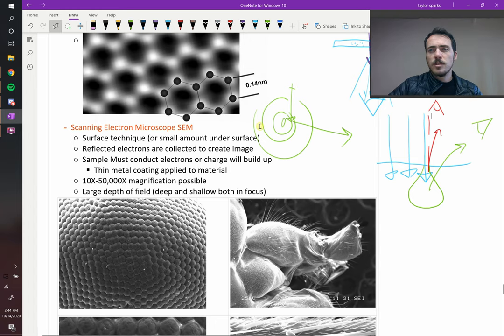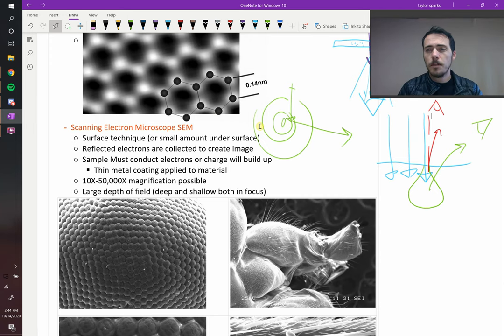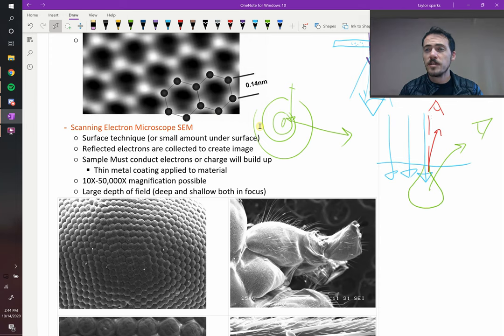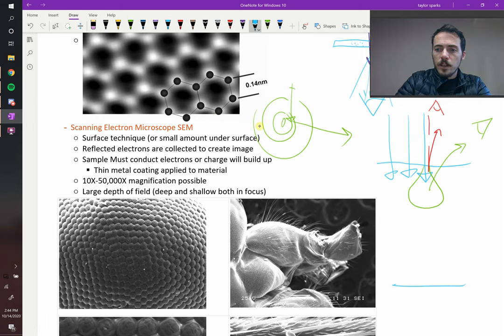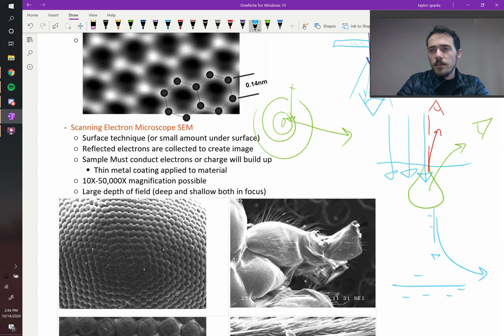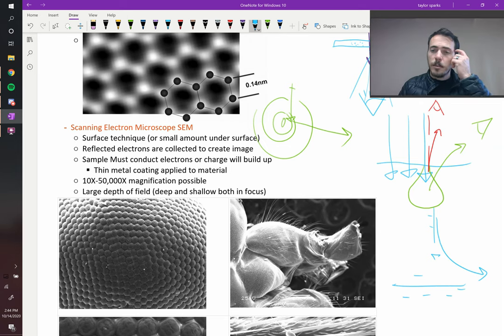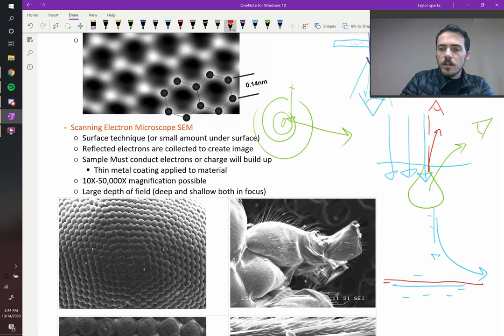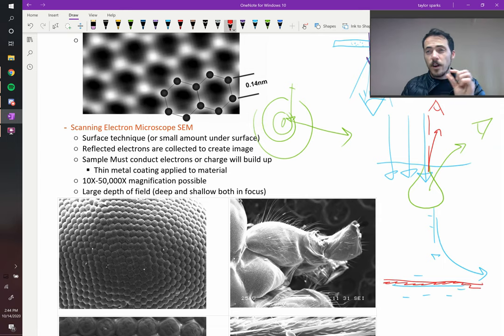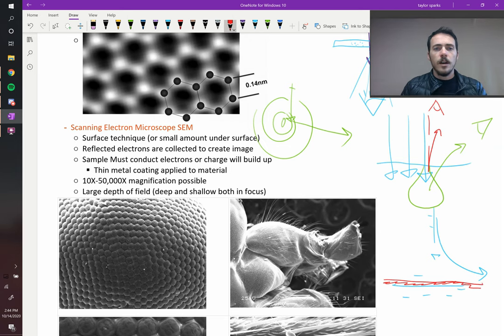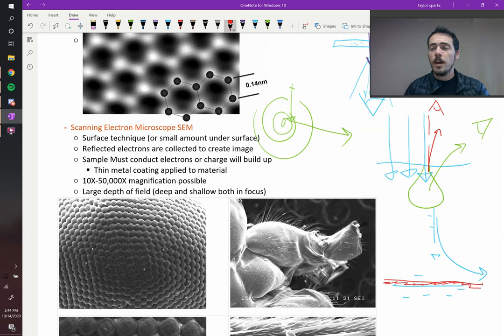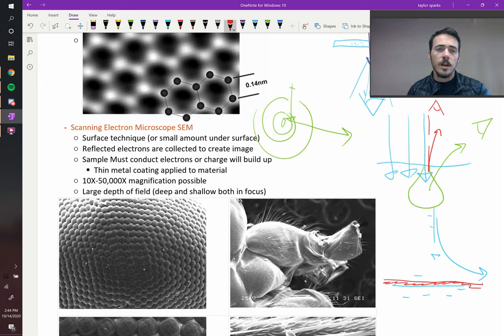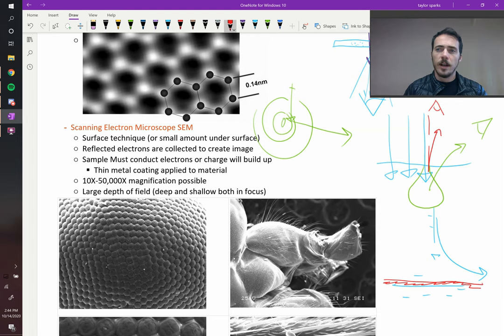Something that happens though is because you're bombarding these with electrons, if your sample does not conduct electricity, what's going to happen? Well, pretty quickly it's going to build up static charge. So if your sample is down here and it's building up lots of negative charge, and then you've got a beam of electrons flying down at it, soon they're going to start to get deflected. So that's not good. That's going to mess up your imaging capability. So what they do is they coat these materials with a very thin coating of something conductive. A little bit of gold or carbon are very common to do. And it's very thin, so you're not spending a lot of money to do this. It needs to be conducting. The typical magnification that you can achieve with a scanning electron microscope, because it doesn't accelerate the electrons quite as fast to crash them all the way through your sample, you don't get quite the same resolution. In fact, you're typically anywhere between 10x and 50,000x. So you can see into the nano regime, but not as far as the TEMs can go.